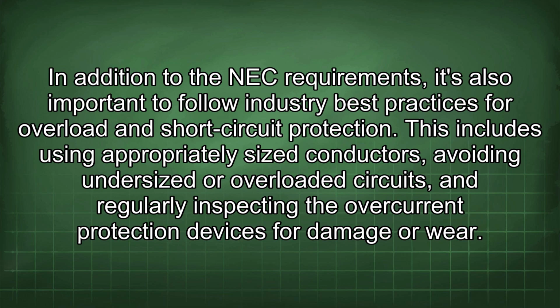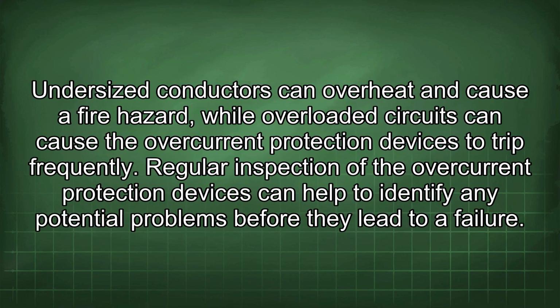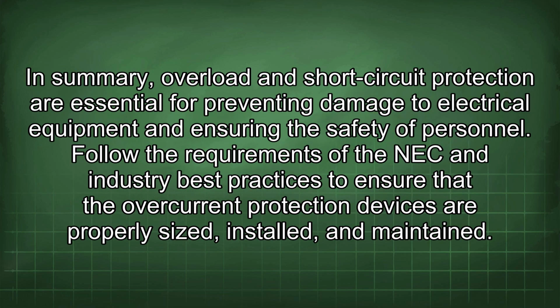This includes using appropriately sized conductors, avoiding undersized or overloaded circuits, and regularly inspecting the overcurrent protection devices for damage or wear. Undersized conductors can overheat and cause a fire hazard, while overloaded circuits can cause the overcurrent protection devices to trip frequently. Regular inspection of the overcurrent protection devices can help to identify any potential problems before they lead to a failure.